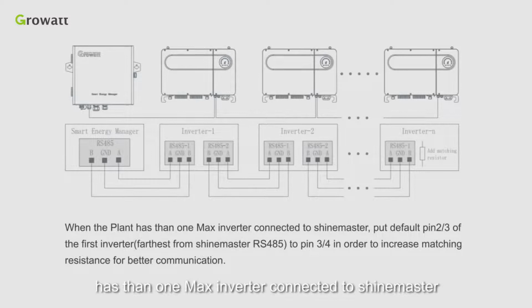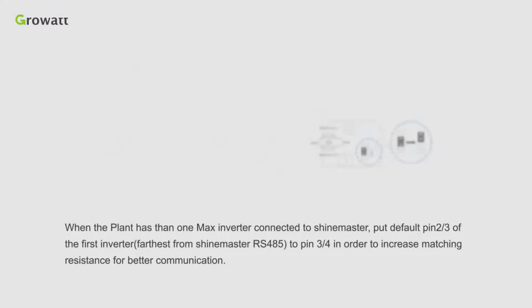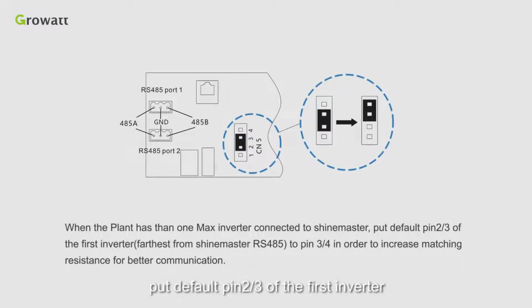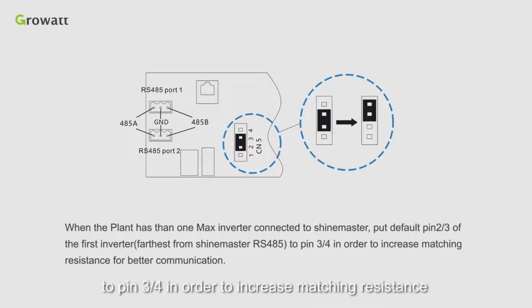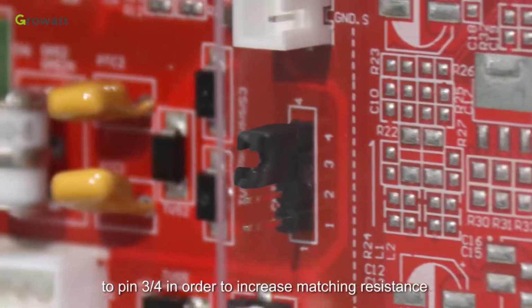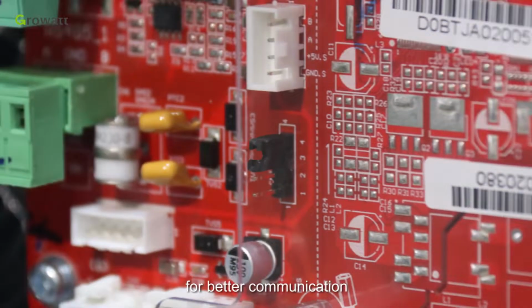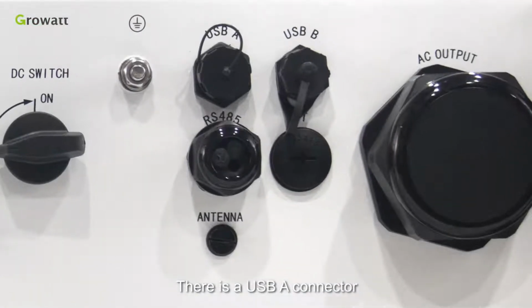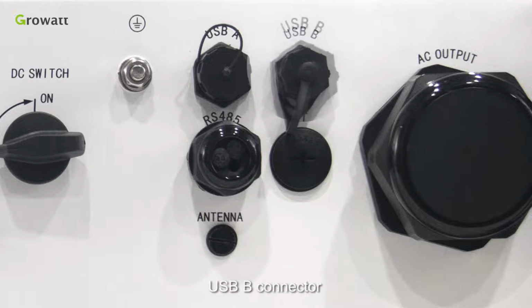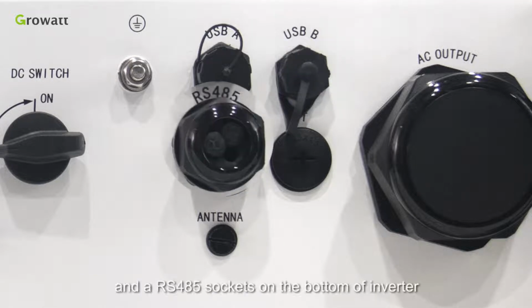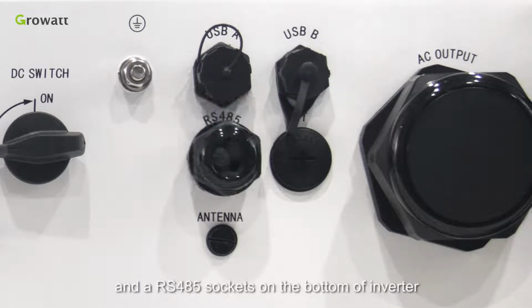When the plant has more than one MAX inverter connected to ShineMaster, the port defaults to pins 2 and 3. For the first inverter, farthest from ShineMaster, change RS485 to pin 3 or 4 in order to increase matching resistance for better communication. There is a USB-A connector, USB-B connector, and RS485 socket on the bottom of the inverter.